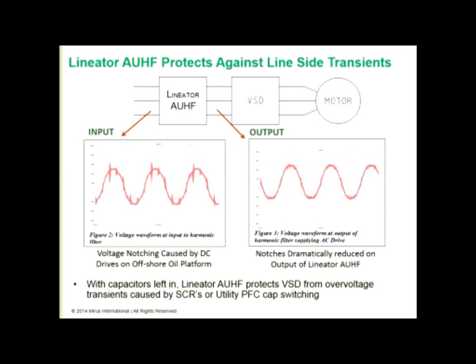And one other thing that we discovered with our filter is that it helps protect the downstream load, such as a variable speed drive. It helps protect it against overvoltage transients and ringing that might be introduced by power factor switching transients by the utility when they switch out their power factor correction equipment. Or in this case, it was due to the rectifiers on the DC drives on an offshore drilling platform.